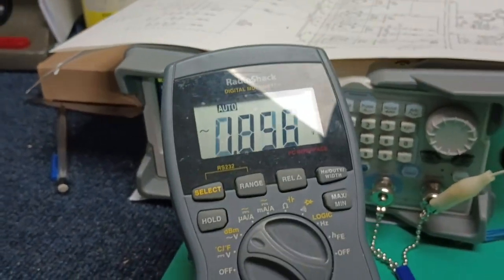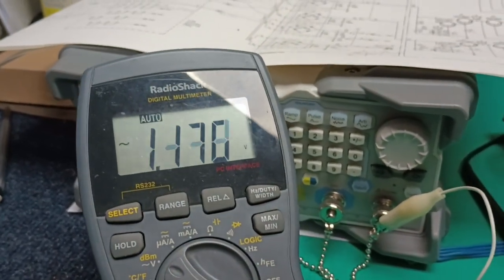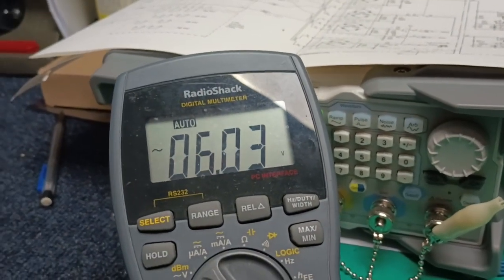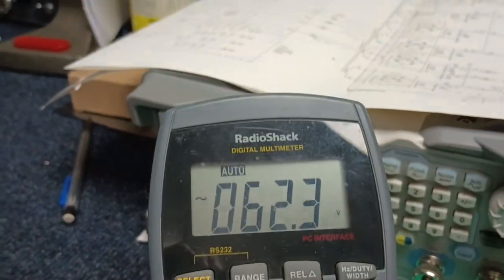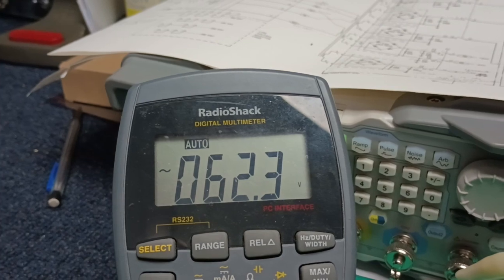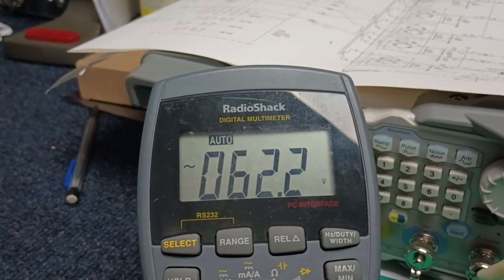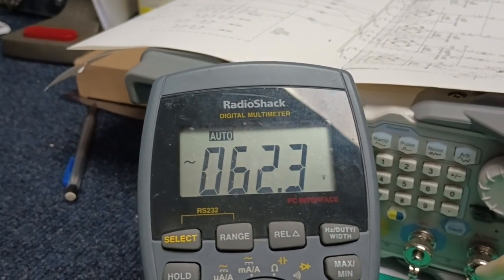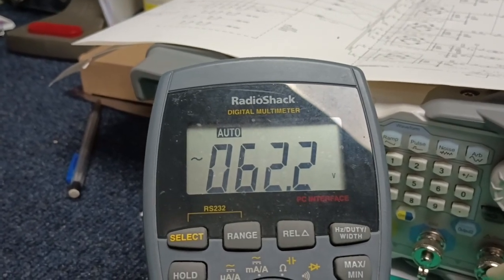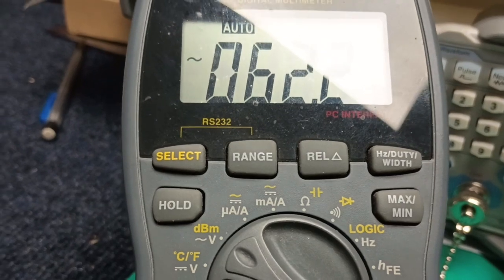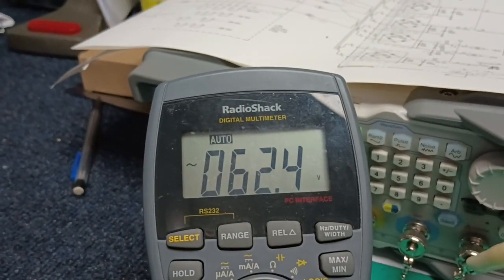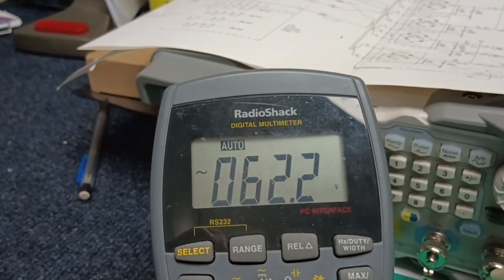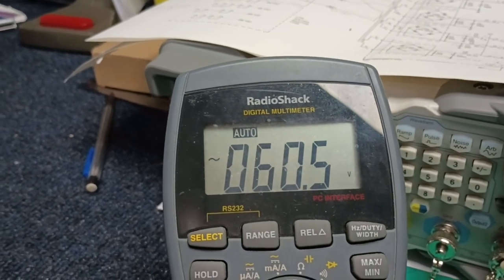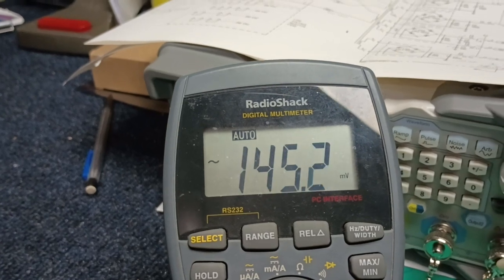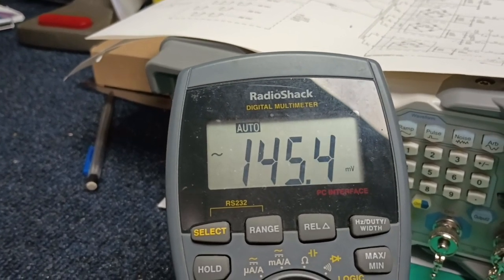We put the meter on AC volts and repeat the experiment with the 20 volt minus supply. That's the minus DC terminal on the 20 volt power supply. A switching power supply reads 62 volts AC. See the AC voltage? Plus terminal, 62 volts AC. Earth terminal, 60 volts AC. Neutral terminal, 145 millivolts.